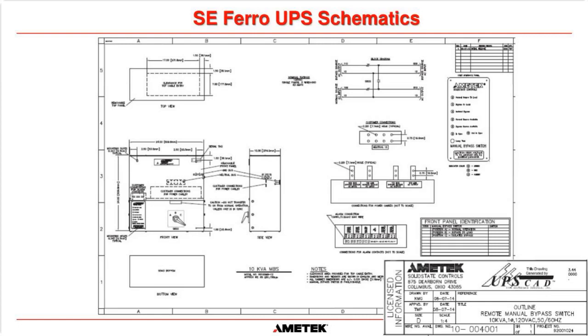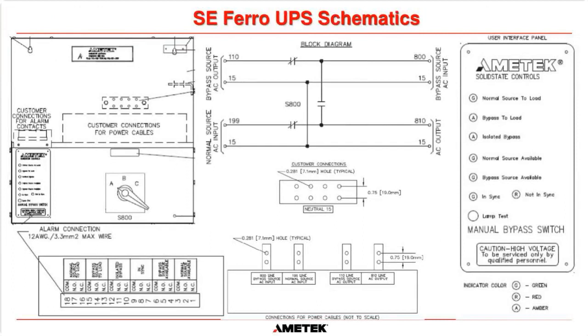So the drawing for an RMBS is usually always separate to the UPS drawing itself. As you can see here, it says sheet 1 of 1, and this is the outline for a remote manual bypass switch. And we're going to zoom in on each portion here. Basically what an RMBS does is it allows us to isolate a UPS for maintenance or replacement and still keep your load circuits powered. But the most confusing thing is if you get shipped an RMBS and a UPS separately, how do you connect them together? And I understand the confusion, but it's actually quite simple. The confusion is usually caused by the wording at these points here. So we have bypass source AC input, bypass source AC output, normal source AC input, and the AC output. Okay.